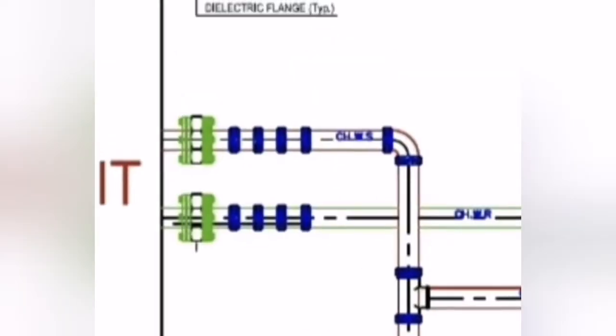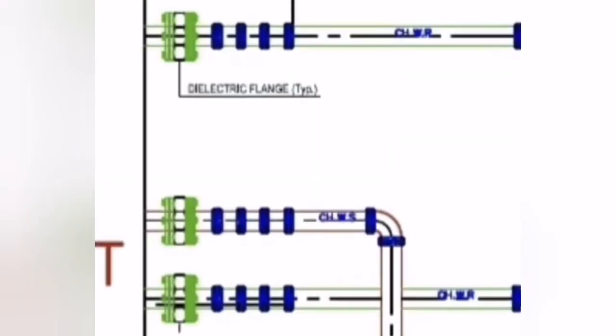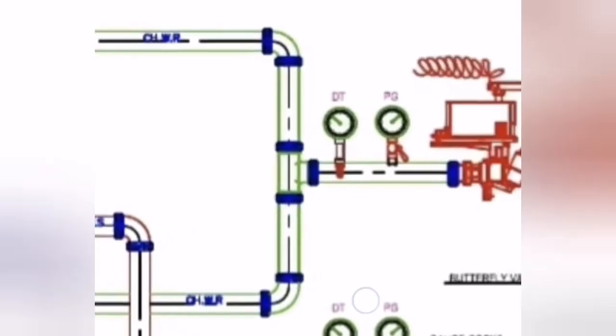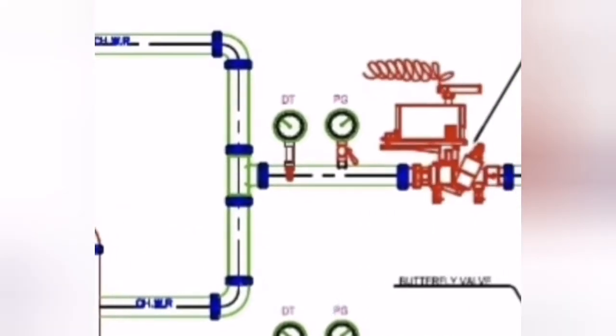And after this I will explain the discharge line. On the discharge line you can see the same flange coupling and the flexible coupling or flexible connectors. These flexible connectors are important on both the suction line and discharge line to avoid the vibration traveling to the pipes. And after this, same thermometer and pressure gauges.